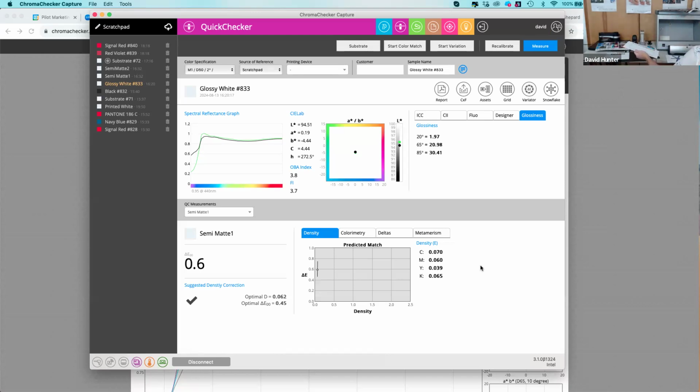And we make the color inspector target in a couple different forms. This is one easily in my hand, which is listed in the ISO 23032 2020 standard for spectrophotometer instruments. But we also worked with Lucideon, who makes the BCRA tiles, which is the only other company listed in this ISO standard for being able to track an instrument. Lucideon worked with us to do a ceramic version of our instrument target. And part of the tool here, we have a couple different versions, both from Lucideon.